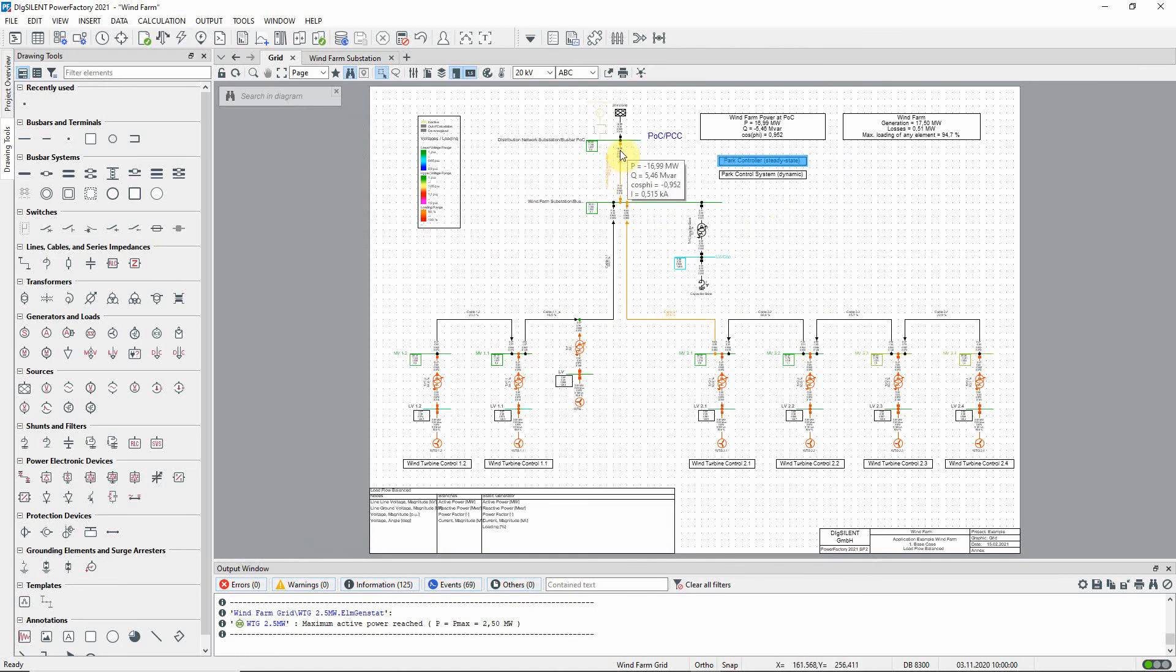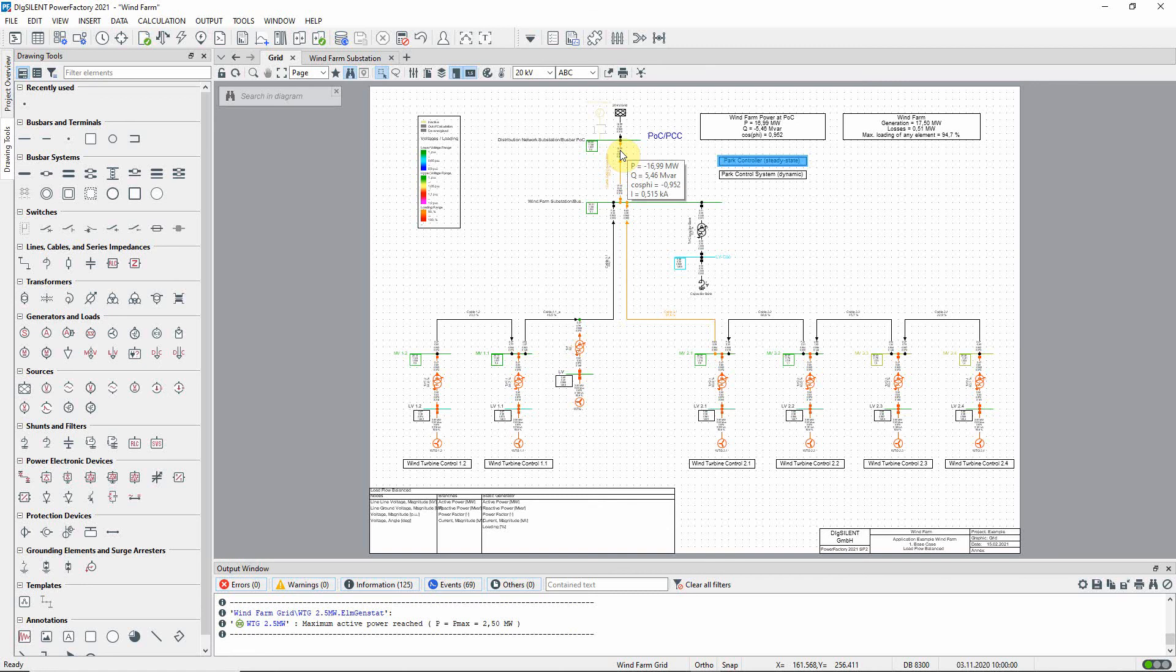You will notice that the active power at the point of common coupling is less than 17.5 megawatts. The power factor is therefore now a little greater than 0.95 in accordance with the updated linear power factor characteristic.